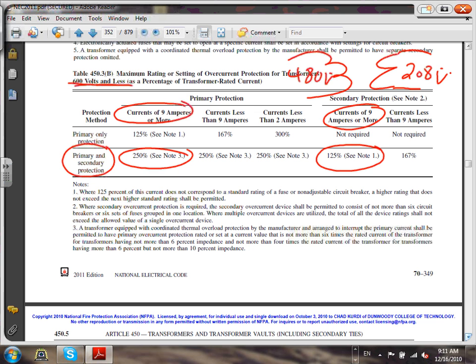On the primary side, it doesn't say fuse or circuit breaker; you can do it for either. On the secondary side, my friend, at a current of 9 amps or more, you're almost always going to be here, and in this application, 125%. Okay, where is it that you don't have to have the secondary protection on it? Cool. That's your tap rules. The tap rules.